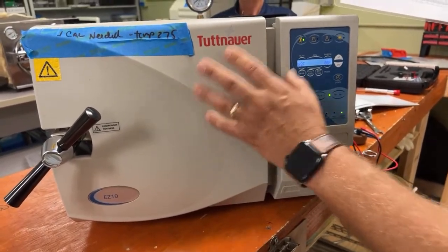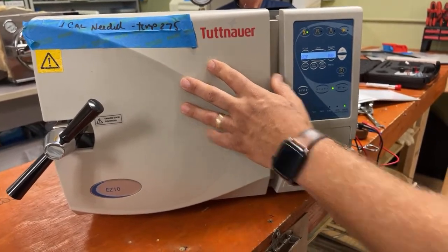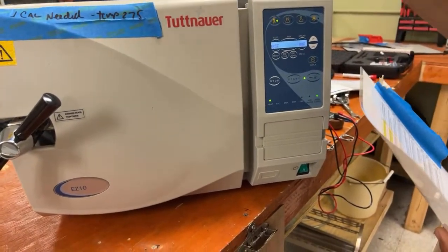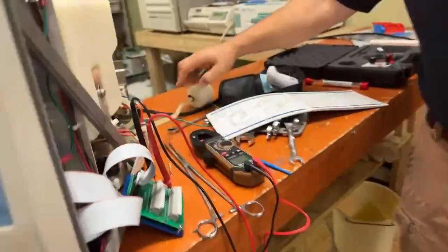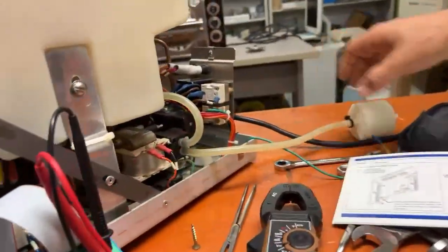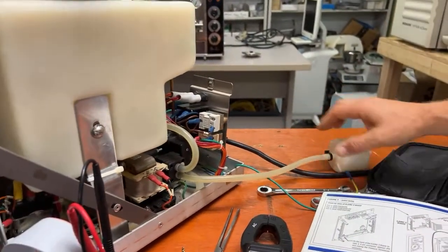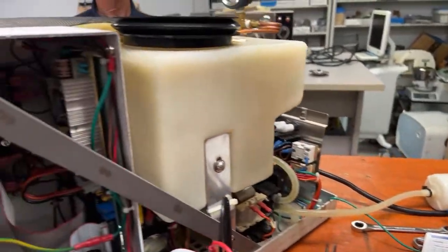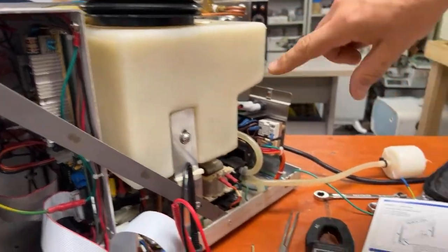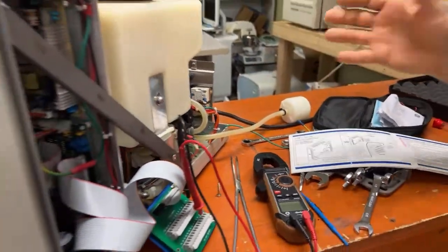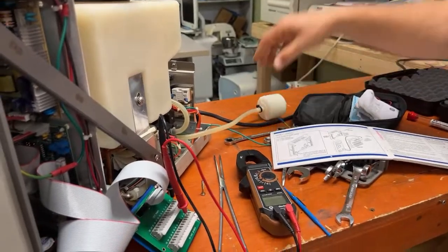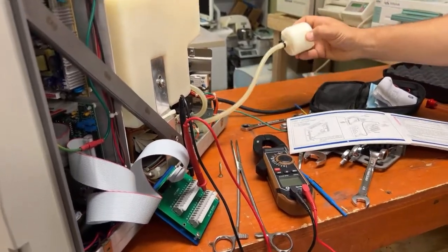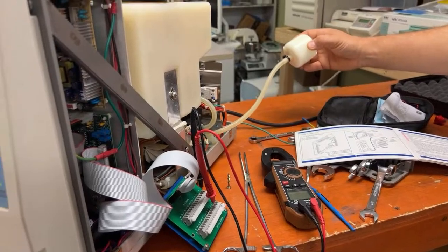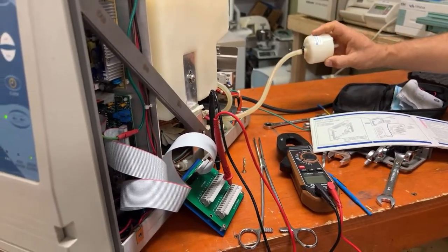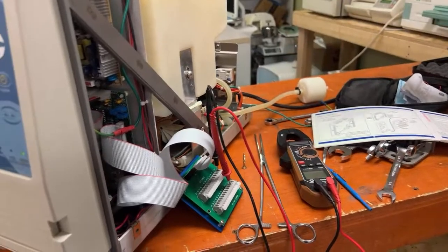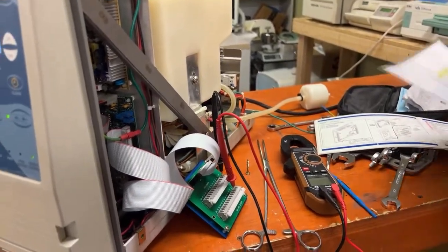And closed door drying means that at the end of the cycle there's going to be a HEPA pump pulling. So there's an air pump right here that moves air through a HEPA filter, and then it pushes it into the chamber, and then it comes out here inside the reservoir. Okay. And what closed door drying does is it allows all the air that's drying everything to be filtered with the HEPA filter, so there are no germs getting into it and getting onto the packs.